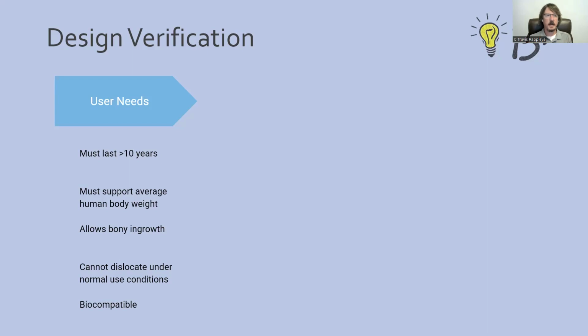And the first step in design traceability is establishing user needs. In case you're unfamiliar with that, this is the starting point for development of a device. It's some physician or somebody that's got a problem that needs a solution, and what they need from the solution, we write out in a list of user needs.